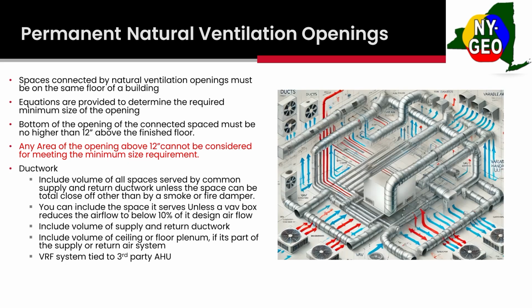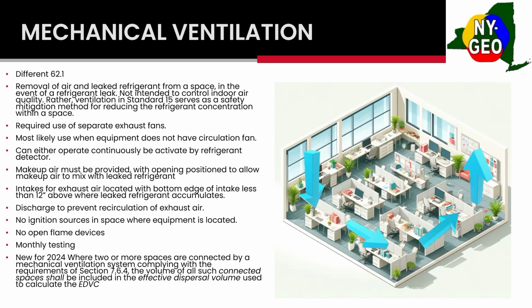Mechanical ventilation gets a little more tricky. The big thing with mechanical ventilation, this is different from 62.1. This is not about air quality. So your DOAS unit does not count for mechanical ventilation. This is strictly a safety mitigation. Mechanical ventilation is used to dilute and remove leaked refrigerant from a space during a leak event, not to condition the air. And you're most likely going to use this for a machine room or any equipment where you might not have a fan to circulate if the RDS goes off.